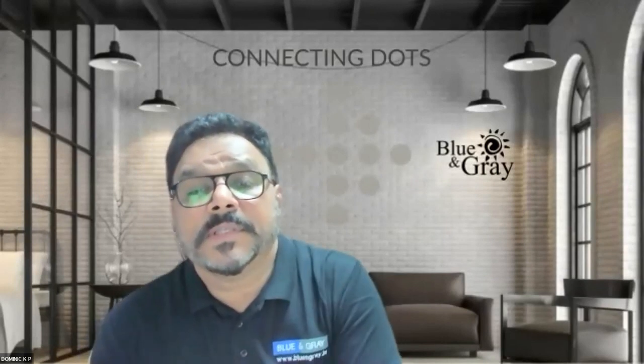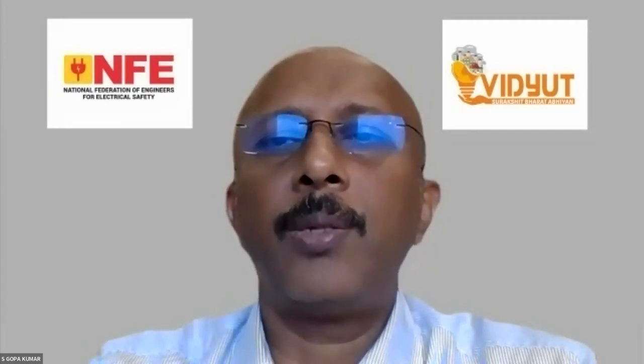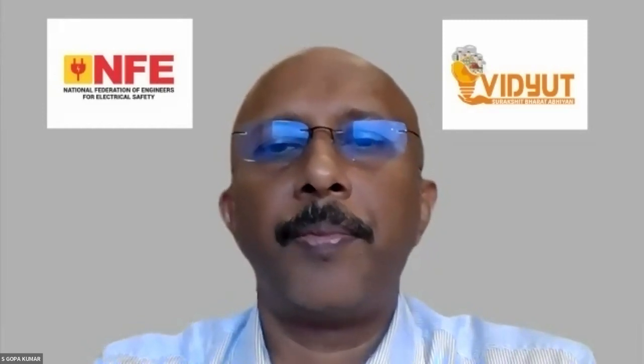Good afternoon, team. Which earthing is best? Common earthing or individual earthing for equipment like X-ray? I don't know. Probably if the question is about individual earthing, what he meant is a separate earth electrode or an earth pit. Please note that this is wrong. So the only good method is interconnection, called protective equipotential bonding.